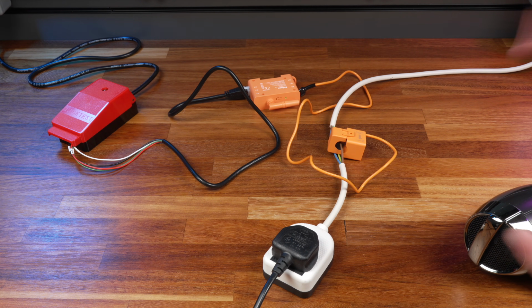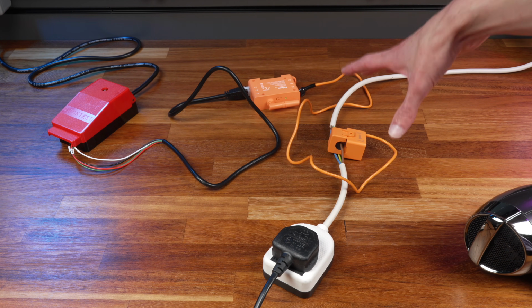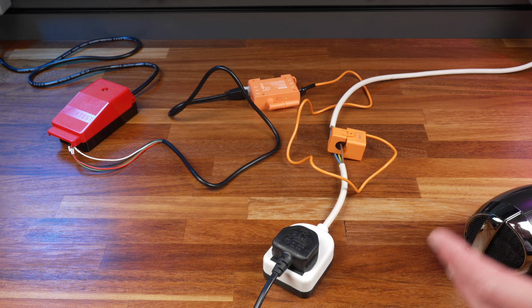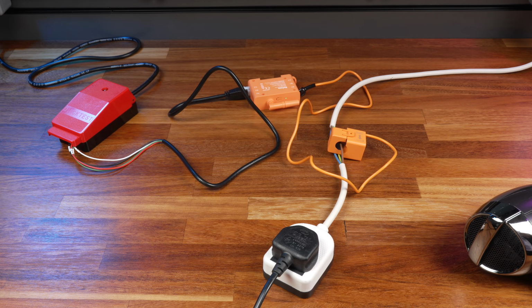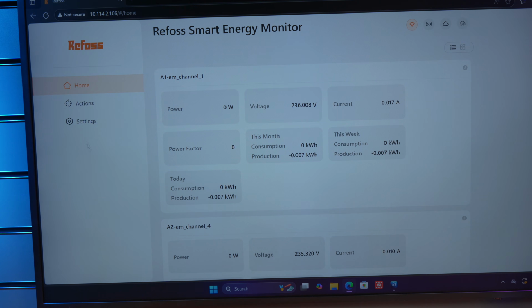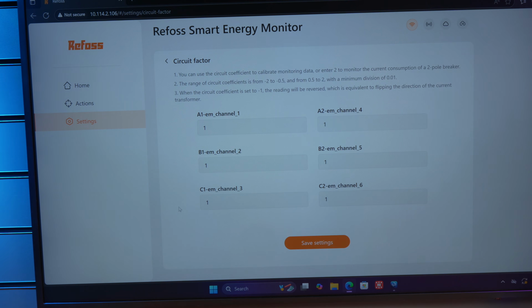What I'm going to do now is check each of my CTs on this test setup and relabel them so that I know the arrow is pointing in the correct direction. I'd also recommend that you do the same just in case. That said, if I hadn't realised this in advance and I'd already installed all the CTs, it's not the end of the world. If we come into the web interface here and go to Settings and Circuit Factor, we get this page here. And these values are essentially multipliers that let you adjust the power readings from each channel.